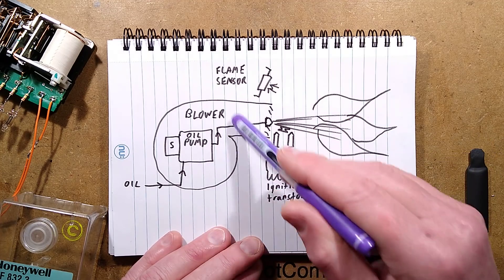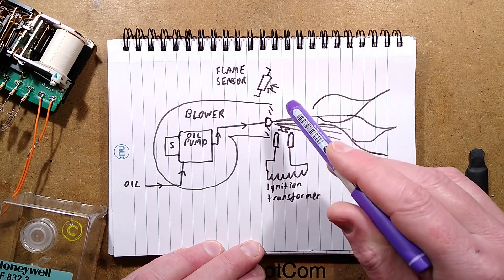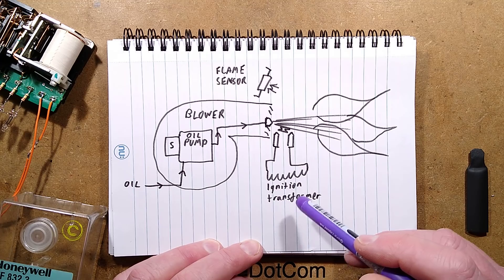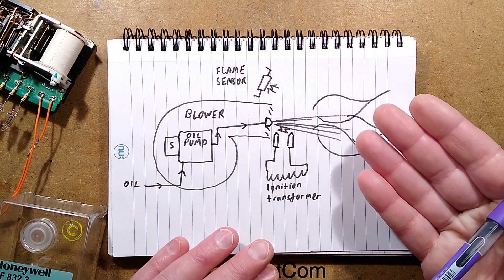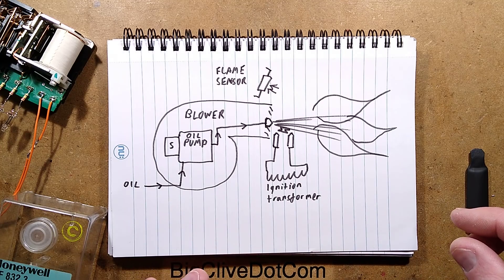And the flame from the very dark cavity in a boiler is detected by the flame sensor, which is set just back behind the airflow to keep it cool. It sends a signal back saying everything's gone to plan, and the system then goes into standby mode, just leaving the blower running and the oil pump running but the ignition off, and just keeps monitoring the flame.